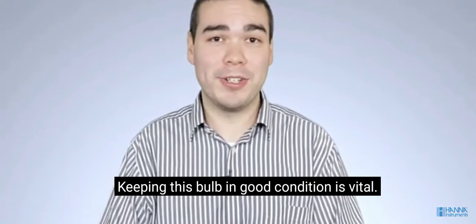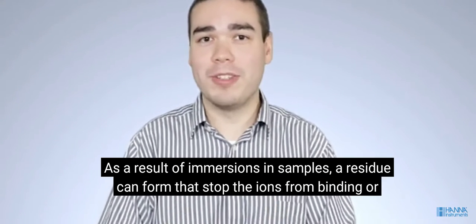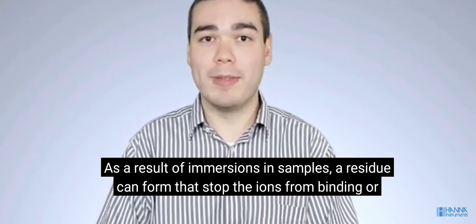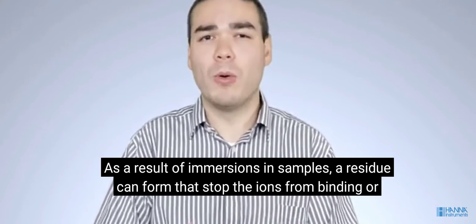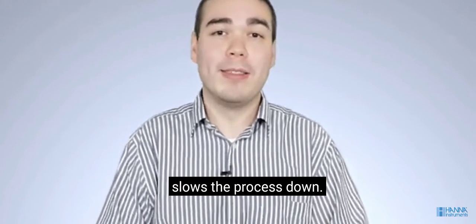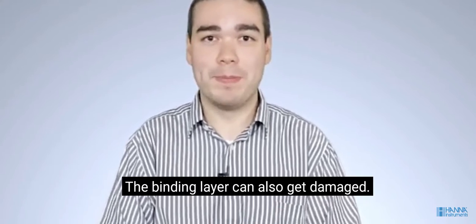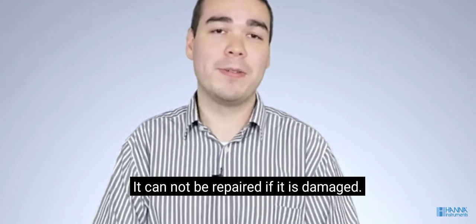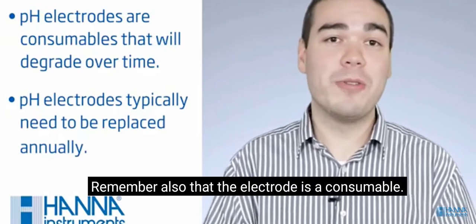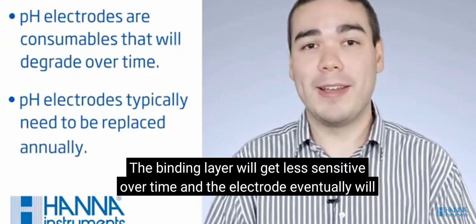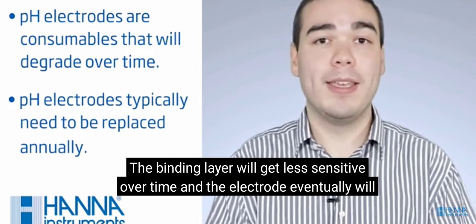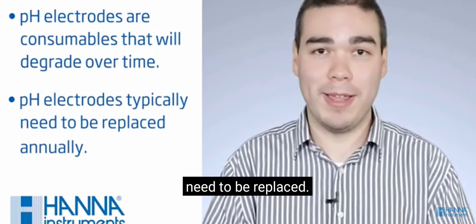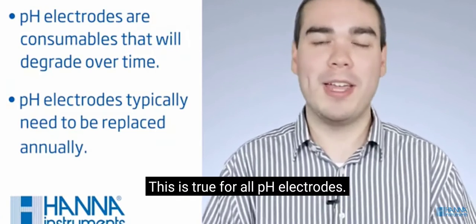Keeping this bulb in good condition is vital. As a result of immersions in samples, a residue can form that stops the ions from binding or slows the process down. The binding layer can also get damaged. It cannot be repaired if it's damaged. Remember also that the electrode is a consumable. The binding layer will get less sensitive over time, and the electrode eventually will need to be replaced. This is true for all pH electrodes.